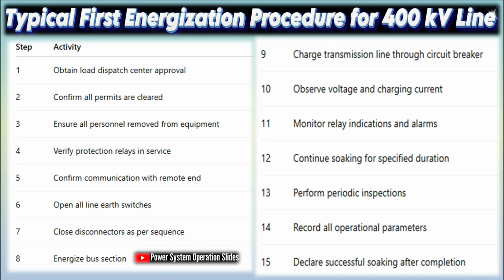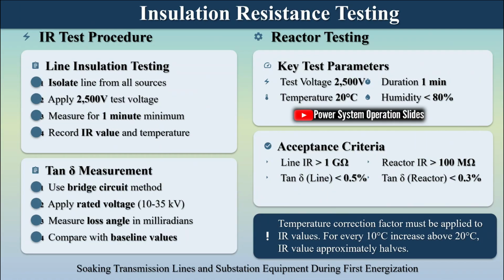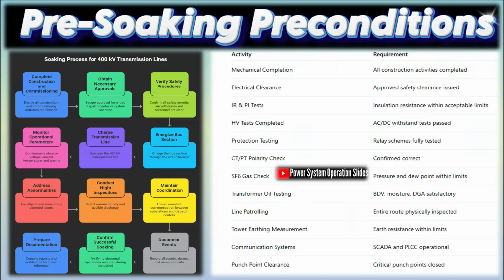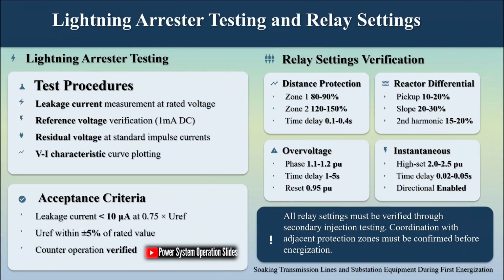During this period, engineers closely monitor insulation performance, leakage currents, and any abnormal discharge activity. This gradual application of voltage allows electrical stresses to be distributed progressively across insulators, conductors, cable terminations, and associated equipment. If hidden defects are present, they are more likely to be detected under controlled conditions rather than during normal operation when failures can have severe consequences for equipment and system stability.